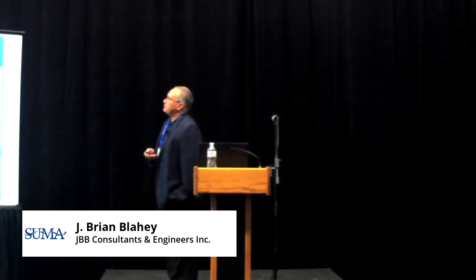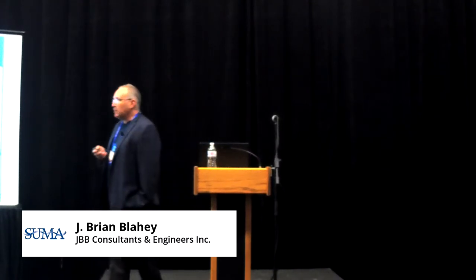HFC 134A is still in production, but is being reduced, and those phase-downs are being sped up. And HFOs are the new blends, or more drop-ins, 448, 449. So in the United States, they've been adopting maximum GWP values that started at about 3,000, dropped to 1,500, 1,500 to 750, 750 down to as low as 150. There are now 26 states that don't allow refrigerants with a GWP greater than 150. That makes it very difficult for new and retrofit rinks.